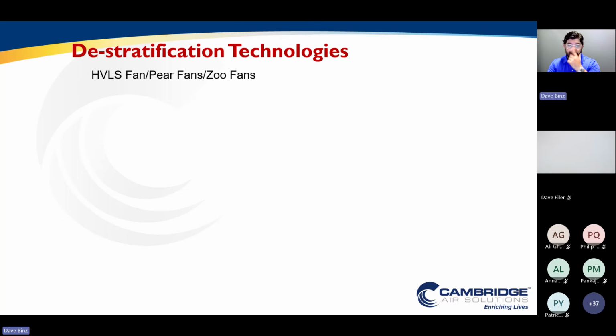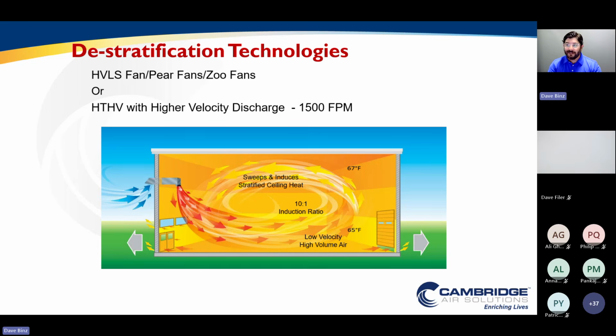There are a variety of ways to deal with destratification. HVLS fans, high volume low speed fans, have become a commonly used solution in existing facilities. However, if I'm trying to solve a ventilation problem, a heating problem, and a destratification problem, what our HTHV solutions can do is actually induce air distribution. It can pull that stagnant warm air at the ceiling down to the floor, utilizing high velocity at a 45-degree angle towards the floor. We can induce about 10 CFM for every 1 CFM of air that's processed by my mechanical fan. So take that 10,000 CFM, 2 million BTU system. By the time I deliver that heat to the space, I have roughly 100,000 CFM of air movement in the space by utilizing that induction principle with high velocity.